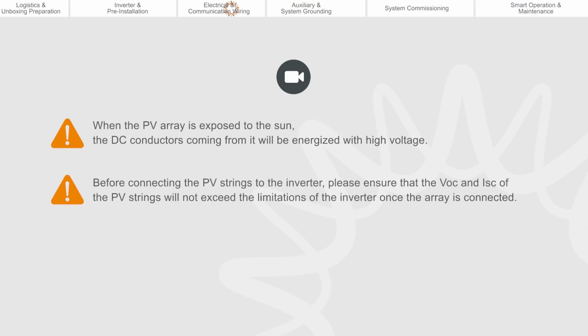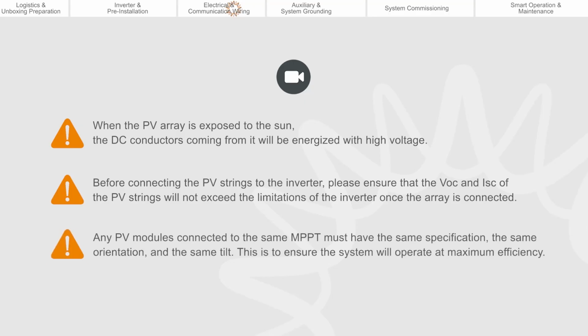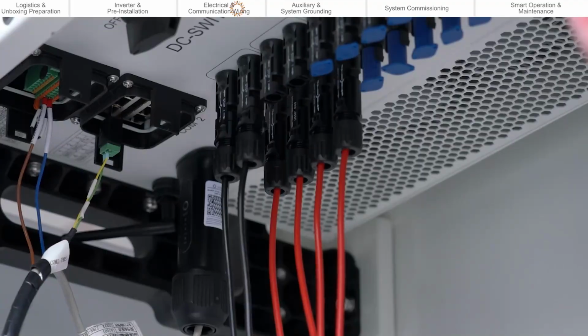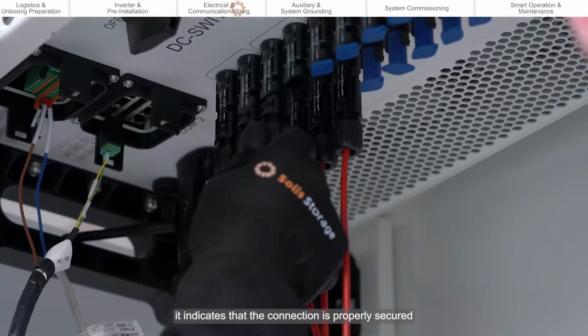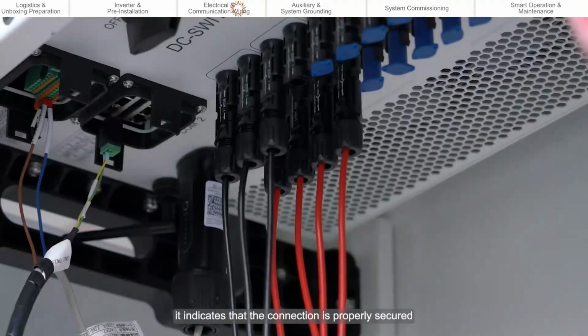Before connecting the PV strings to the inverter, please ensure that the VOC and ISC of the PV strings will not exceed the limitations of the inverter once the array is connected. Any PV modules connected to the same MPPT must have the same specification, the same orientation, and the same tilt. This is to ensure the system will operate at maximum efficiency. When you hear a click sound, it indicates that the connection is properly secured.